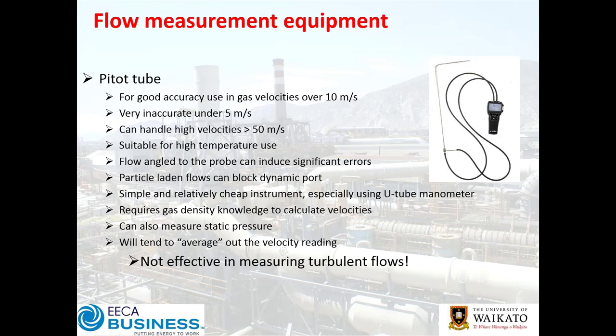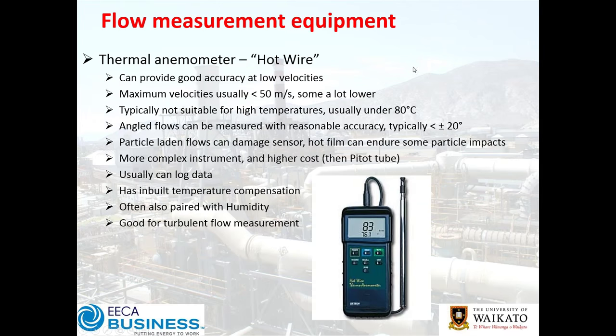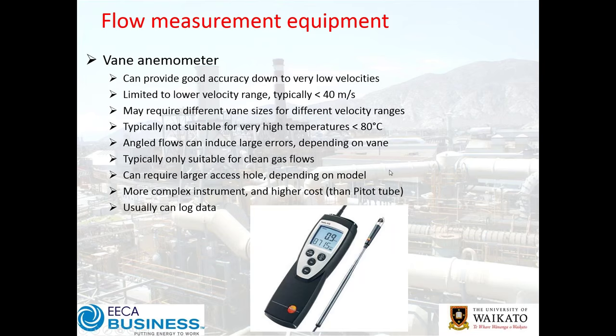If you've got turbulent flow, a hot wire is probably the way to go — good and accurate at low velocities, though with an upper velocity limit and typically a temperature limit unless you have a very expensive one. The downside is it measures flow over a relatively large angle, so immediately after a fan where you've got in-plane velocity components, you're going to overshoot. Provided you understand that and compensate accordingly, it comes back to good selection of measurement location.